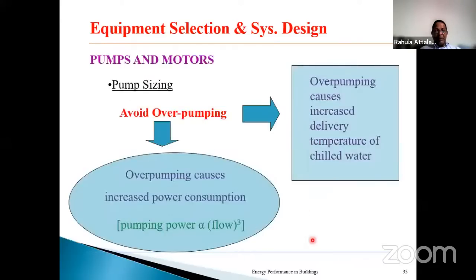Under equipment, all the central chillers will have some level of fan or pump, and this will indicate how the fan or pump should be properly used, because the flow rate will have to be varied, and therefore pumps and motors have to be selected accordingly, mainly to consider the variable flow conditions. Just noting that pumping power is proportional to the flow to the power 3, so a slight variation in flow can affect the pumping power. This is by the laws of fluid mechanics, and therefore pumping will be affected by the variation of flow conditions, and this can be taken as an advantage.